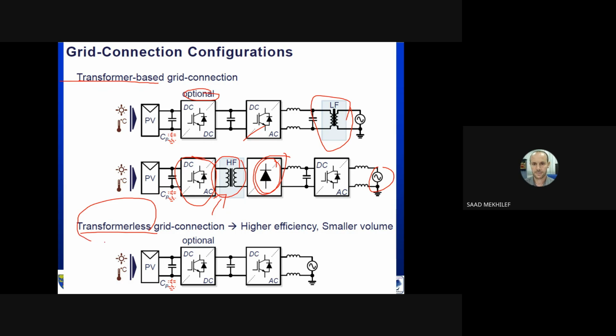Okay. Also, we have the transformerless topologies. And this topology does also exist in the market. You are either looking for transformer or transformerless. For the transformerless, you can see we have eliminated the transformer altogether. Okay, in terms of efficiency it is better, in terms of size it is smaller, but the problem is there is no isolation. So the problem of leakage current is an issue. There are methods on how we can control the leakage current, okay? Because in terms of safety, it becomes an issue, very unsafe.